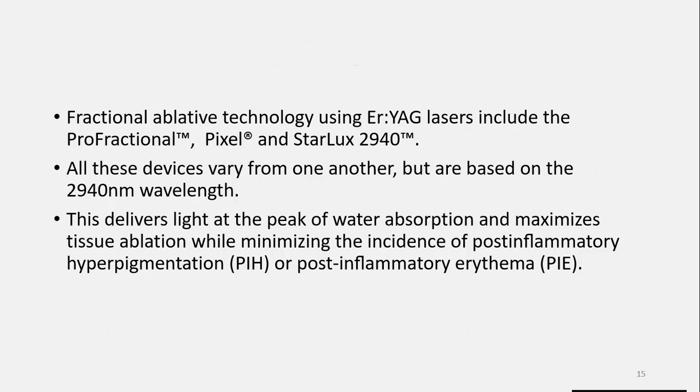Fractional ablative technology using erbium YAG lasers includes the ProFractional, Pixel, and Starlux 2940. All these devices vary from one another but are based on the 2940 nanometer wavelength, which is the wavelength of the erbium YAG laser. This delivers light at the peak of water absorption and maximizes tissue ablation while minimizing the incidence of post-inflammatory hyperpigmentation as well as erythema.